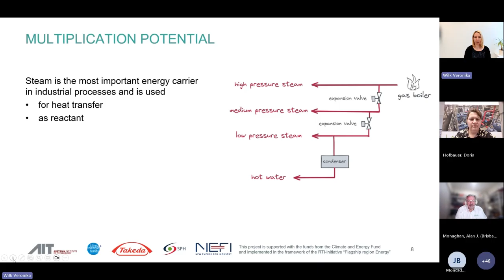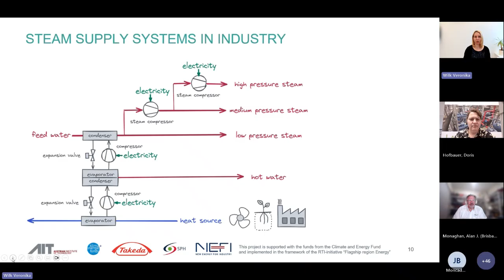If we do this with a heat pump system, we have to flip the perspective upside down. We start with the heat source, with a closed loop heat pump that produces hot water, and another heat pump that then produces steam in the condenser, very similar to the system implemented at Takeda. For the remaining consumers that need higher pressures, we add steam compressors to meet the temperature and heat demand within the process. In the end, we can switch off the gas boiler and run the complete system on renewable electricity.